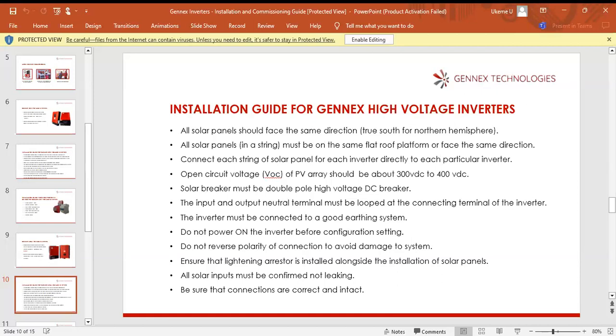You don't have to experience hacking or a breaker catching fire because you're not using the right one. The input and output neutral terminal, like I mentioned earlier on, must be looped together at the connecting terminal of the inverter. This is applicable to all our inverters. The inverter must be connected to a good earthing system.